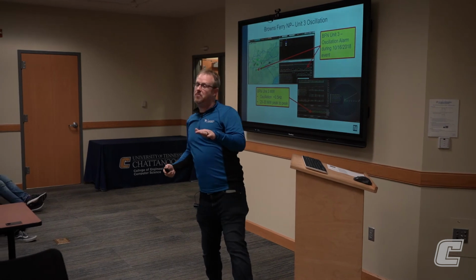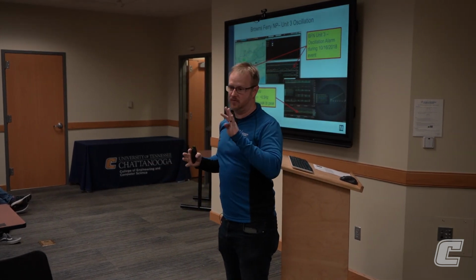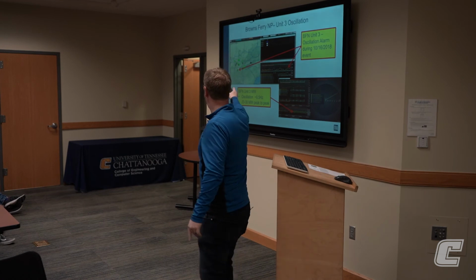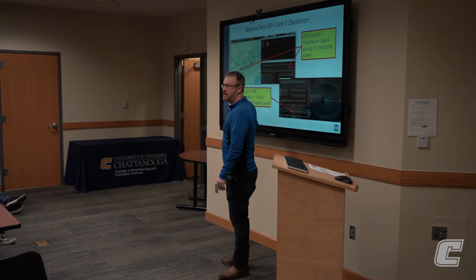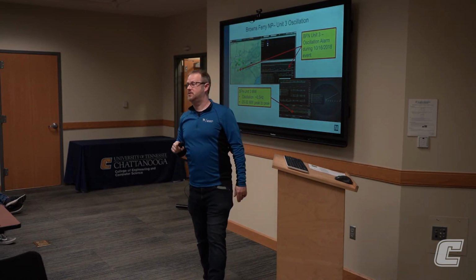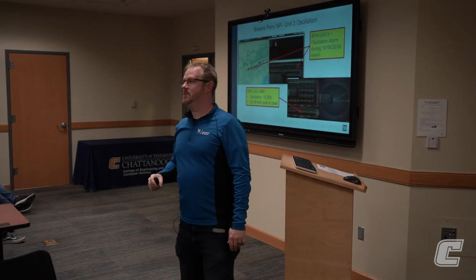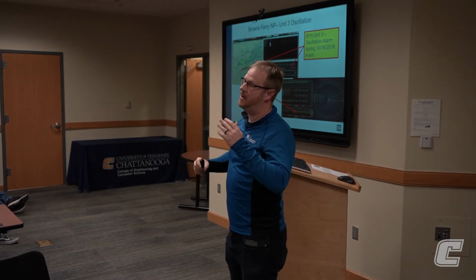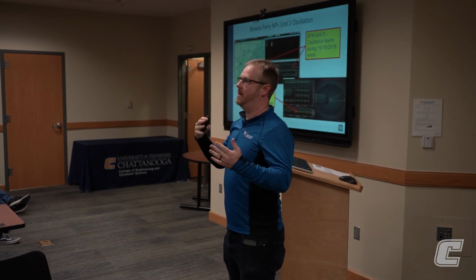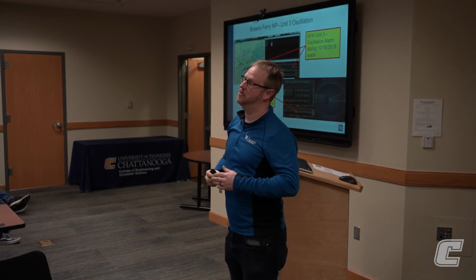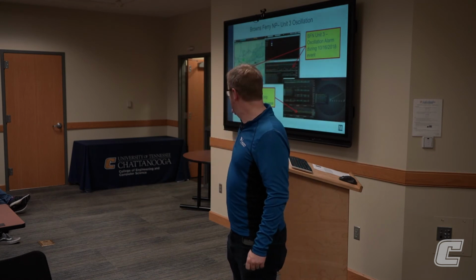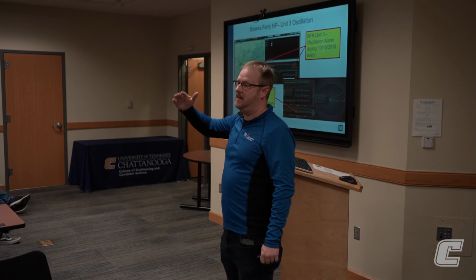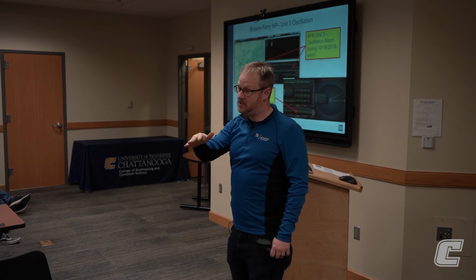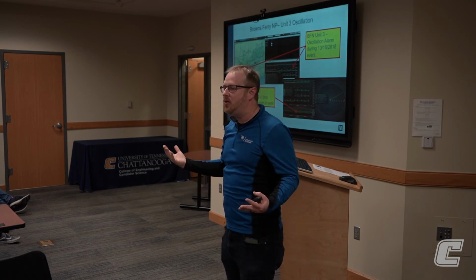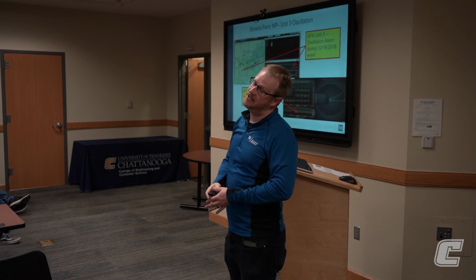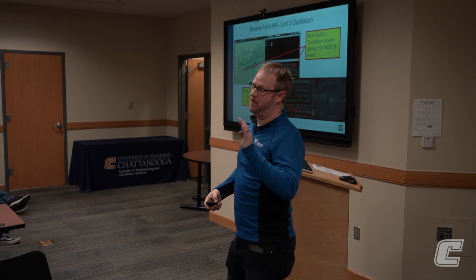The main point of the paper was to call out those 4 natural frequencies so that if you were to have a Brown's Ferry start oscillating at 0.25 hertz, you'd know you could start moving the whole grid. So it's to provide that awareness. In the future, we want more of that embedded in the industry, so that if you start oscillating at that frequency, you get heightened alarms or your plants know about it. It's very new, so we're all still trying to learn, but yes, those 4 natural modes are very important.